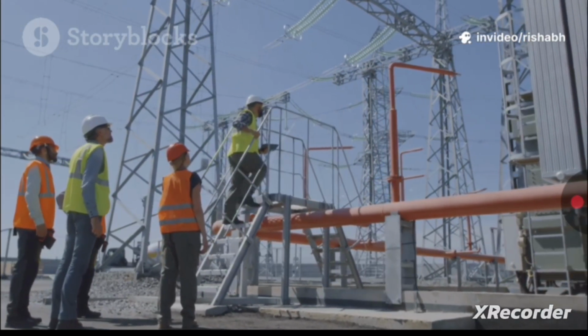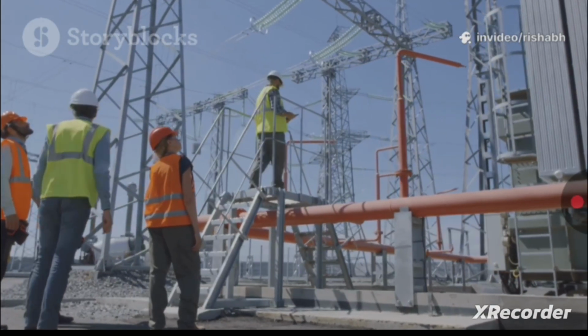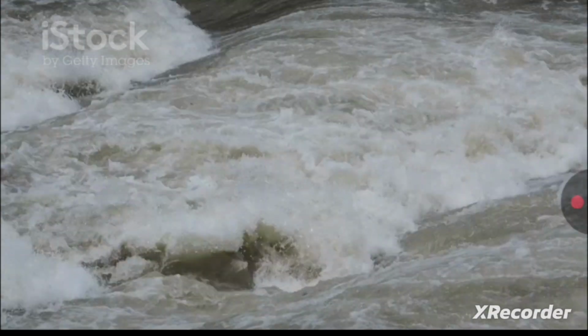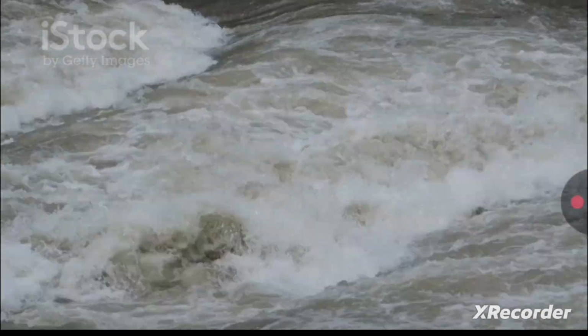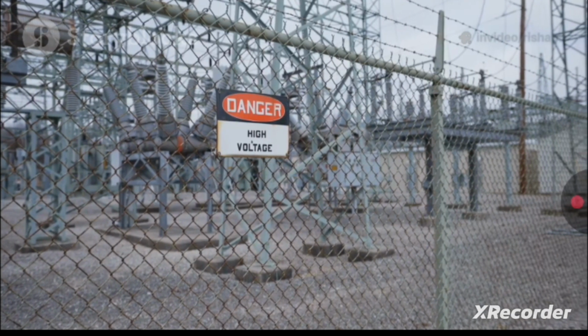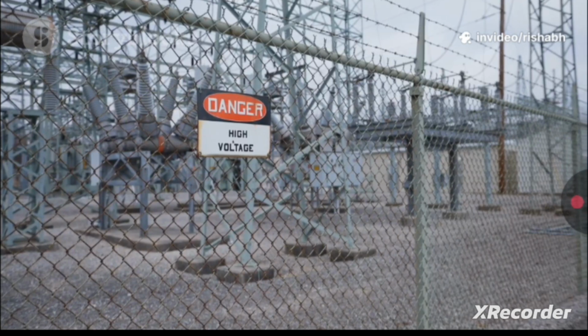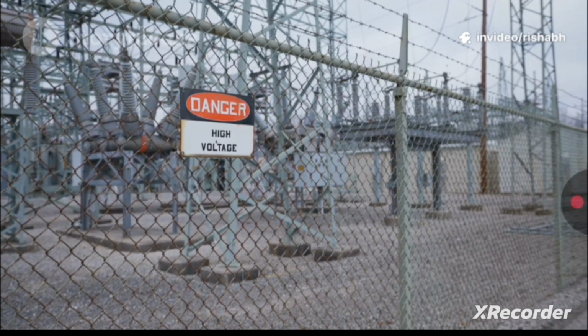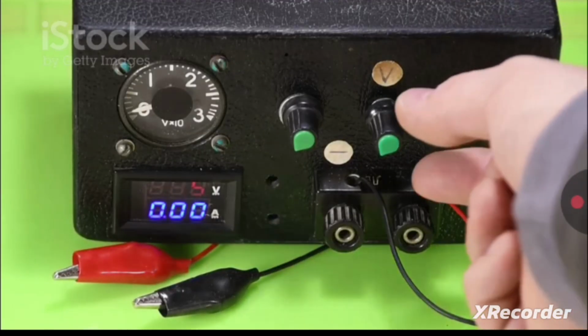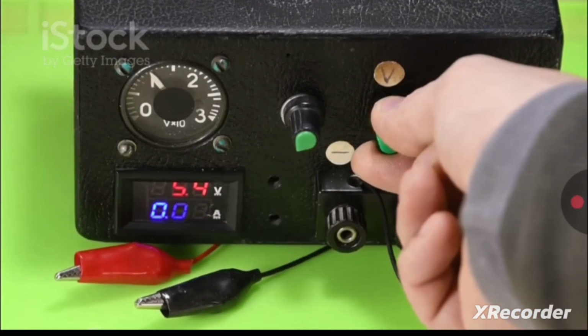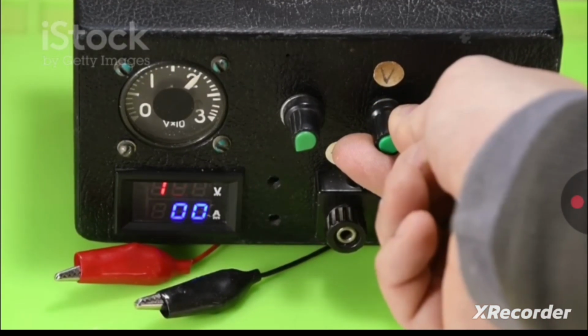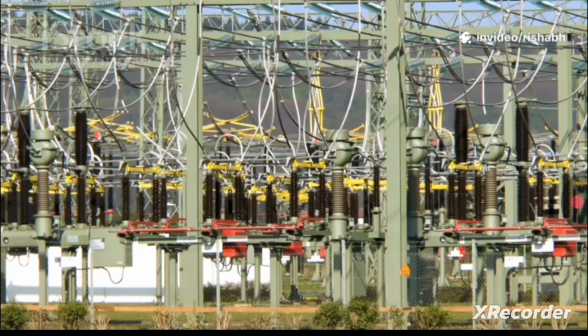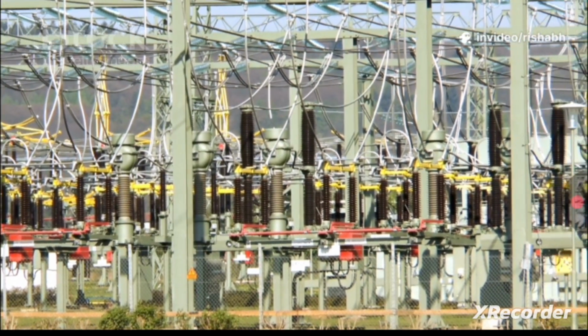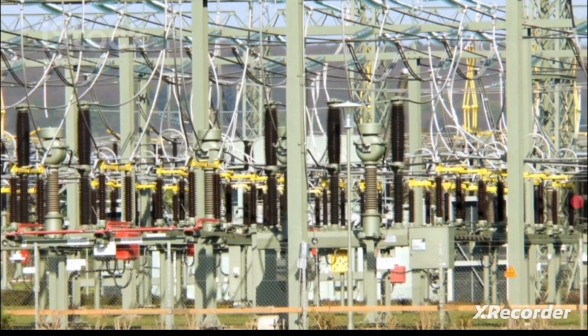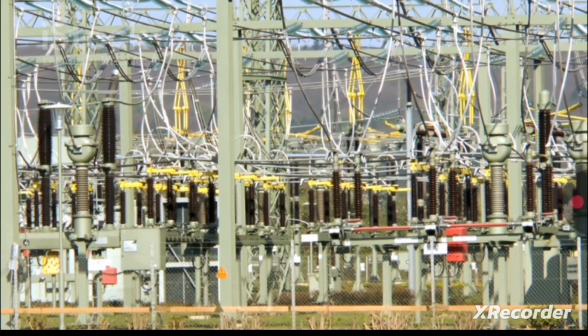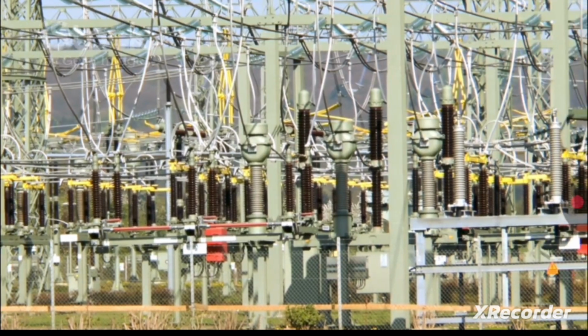So, what happens when that perfect voltage over frequency balance is disturbed? Imagine our well-behaved river of magnetic flux turning into a raging, overflowing flood. This is what we call over-fluxing, or over-excitation. It happens when the voltage over frequency ratio exceeds the transformer's design limit. This can occur in one of two ways. Either the voltage gets too high while the frequency stays the same, or the frequency drops while the voltage remains constant. In both scenarios, the result is the same. The transformer is forced to create more magnetic flux than its core was ever designed to handle. It's a recipe for trouble.